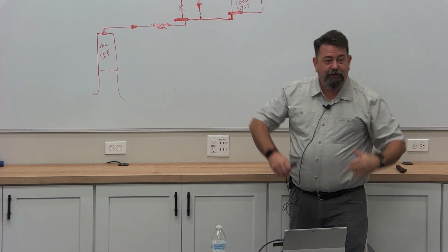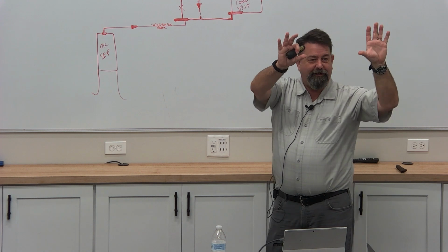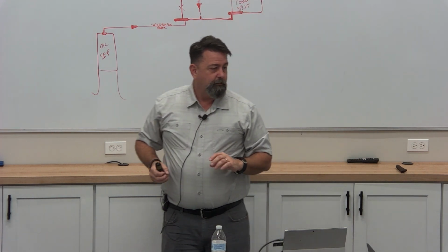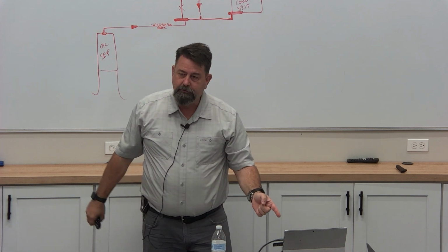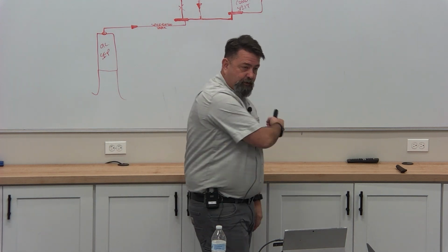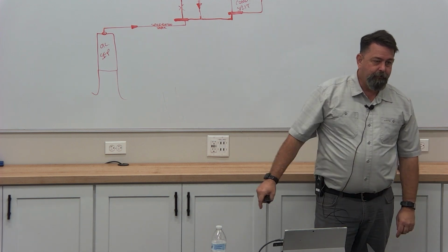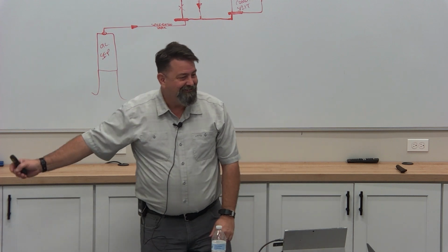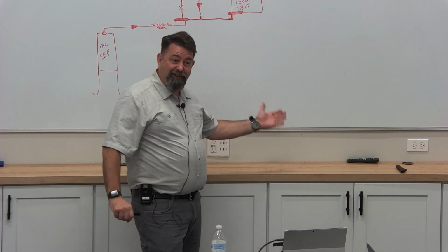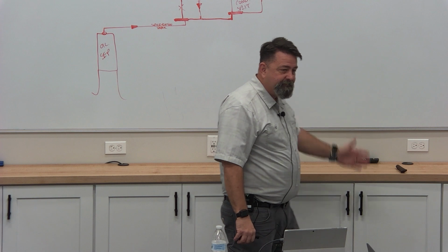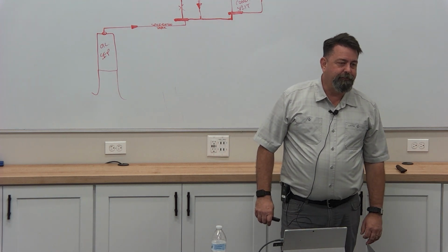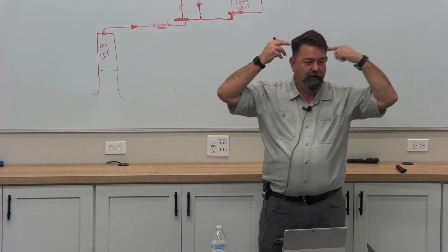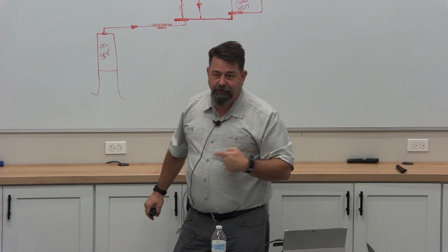And then they do a remodel and have us take that off and they put something new on the wall instead. Who re-aimed that duct? Nobody. Now it's washing out a case it didn't before. If we're the unlucky ones that just changed that case, and we put in a brand new case that doesn't work, they ask, the old one did, this one didn't, what changed? We don't even think that we just moved that sign. I didn't, the startup guy didn't.